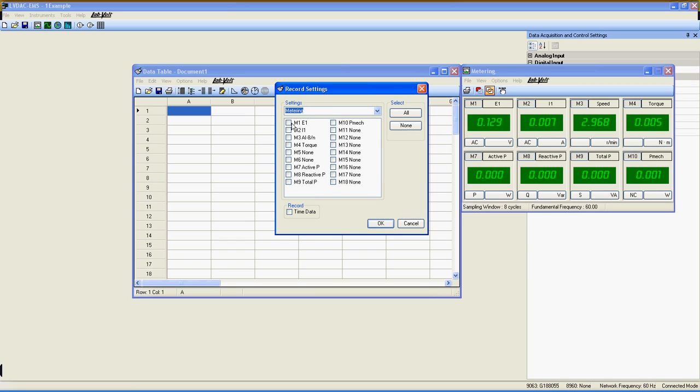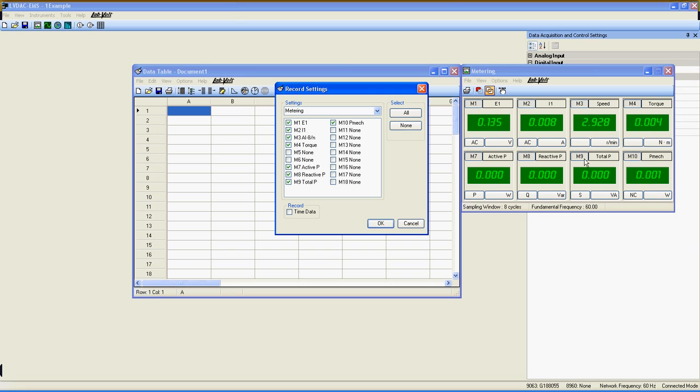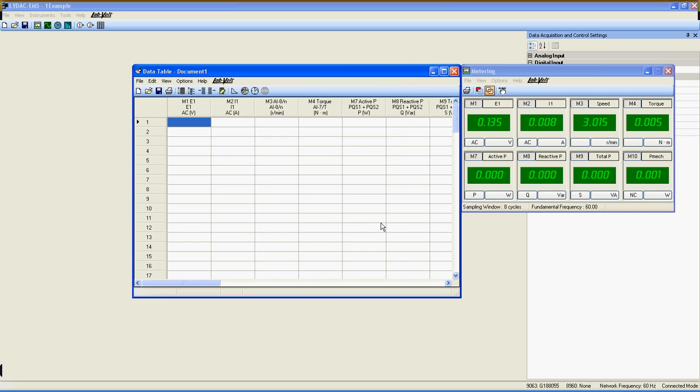Once selected, just go here and select which meter you want to add to the data table. Their numbers and names are exactly the same as in the metering window. In this case, meters 1, 2, 3, 4, 7, 8, 9, and 10 are used, so I will select only those. Once done, click OK.